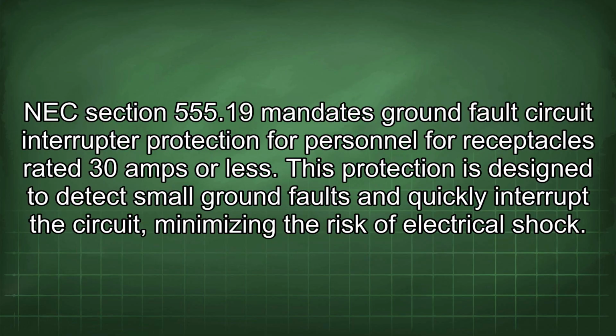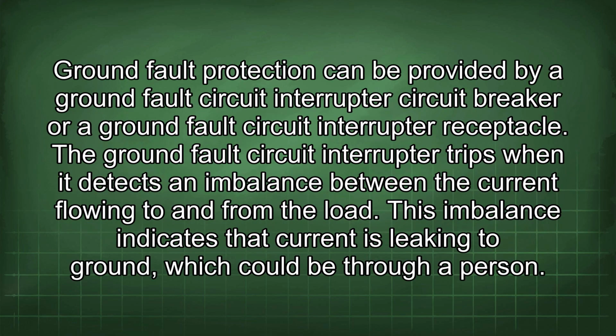NEC Section 555.19 mandates ground fault circuit interrupter protection for personnel for receptacles rated 30 amps or less. This protection is designed to detect small ground faults and quickly interrupt the circuit, minimizing the risk of electrical shock.